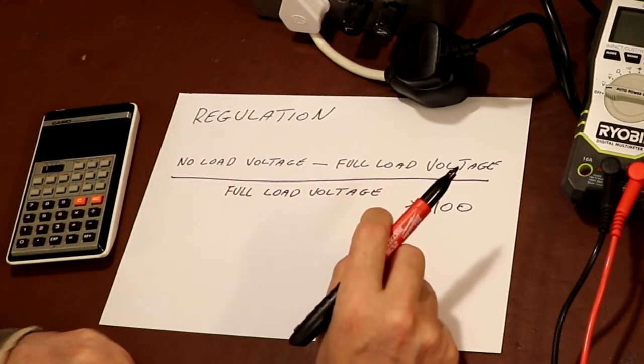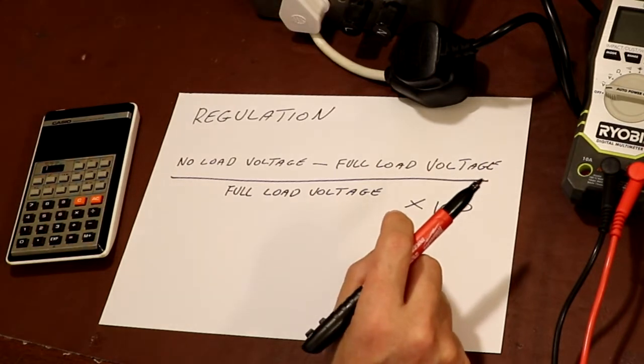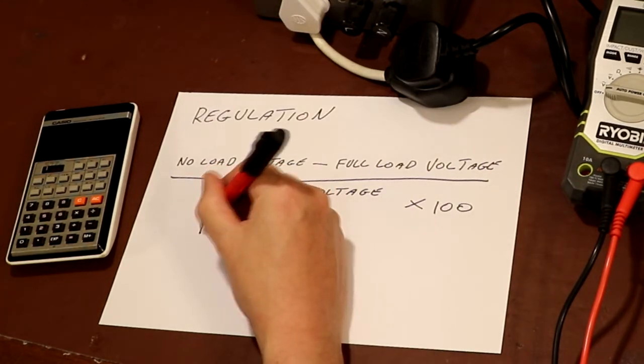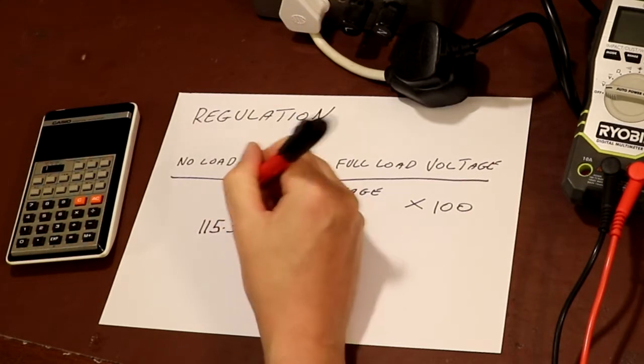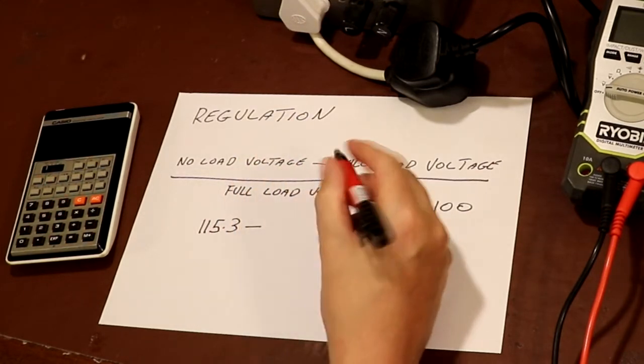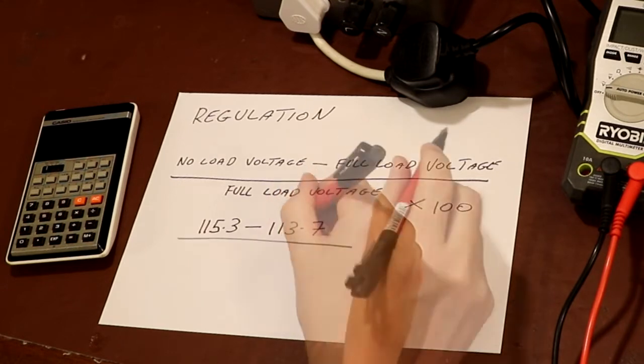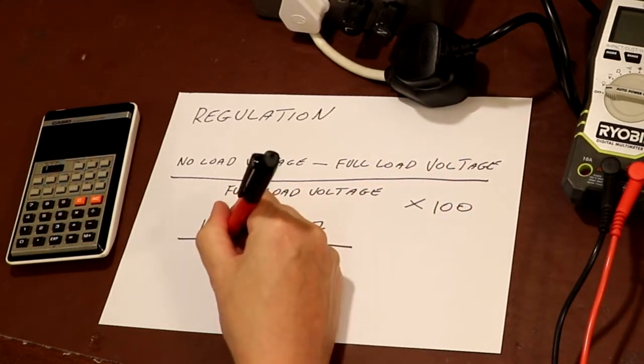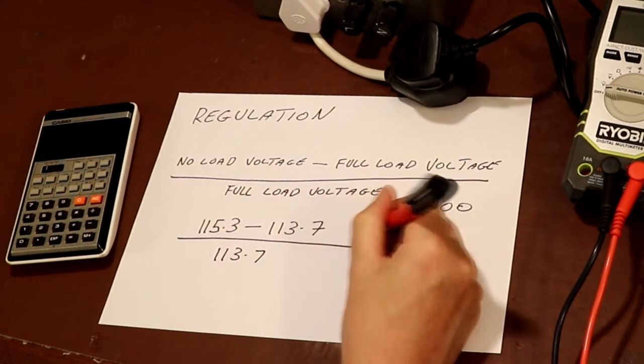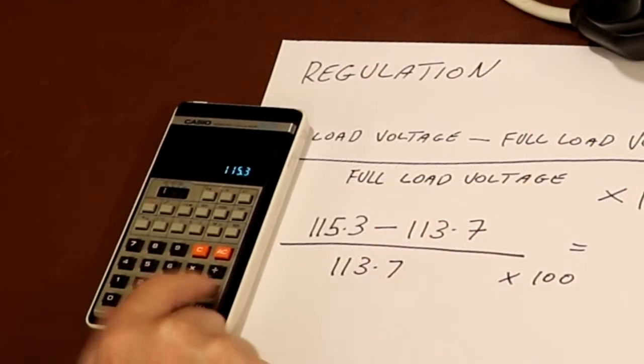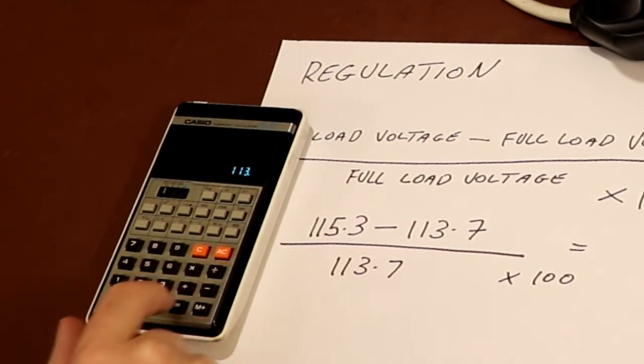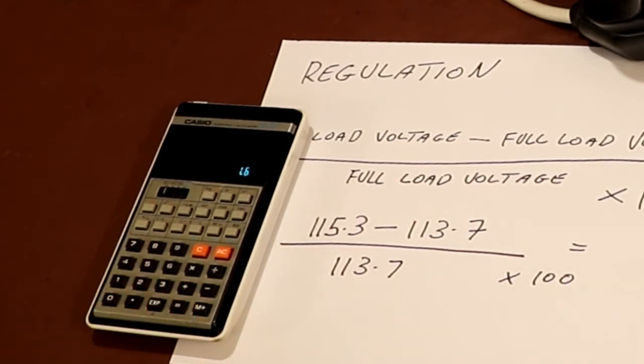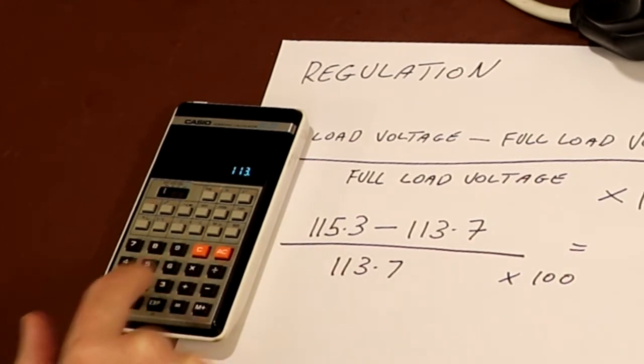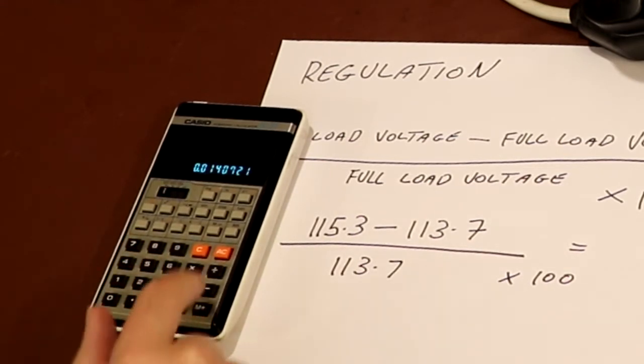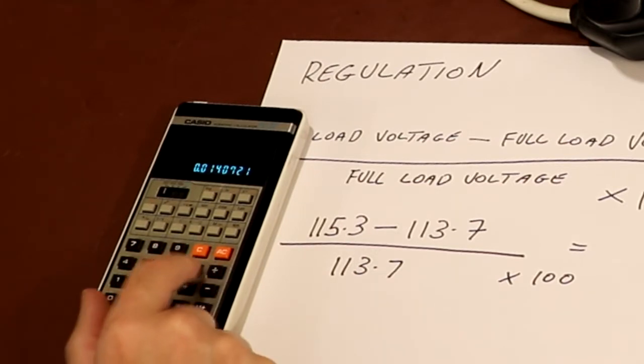Our no-load voltage, recorded when the radiator was switched off, was 115.3 volts. And we had a full load voltage of 113.7 volts. So we take 115.3 minus 113.7, which equals 1.6, divided by 113.7 equals 0.01, multiplied by 100.